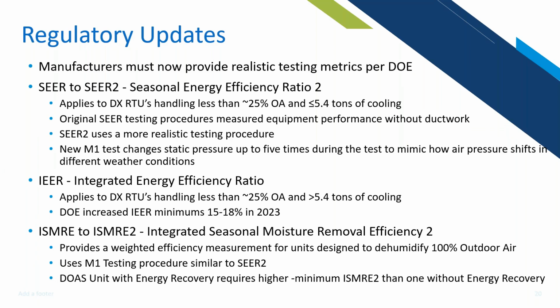Some other changes in regulations: manufacturers now need to provide more realistic testing metrics per the DOE. So you're going to start seeing nomenclature like SEER2. SEER has always been thrown around. It's the seasonal energy efficiency ratio, and that applies to DX rooftop units handling less than 25% outside air and less than or equal to 5.4 tons of cooling. The original SEER testing procedures were not as realistic because they were measured without ductwork, but SEER2 uses the new M1 test procedure that adds static pressure to the system and weights it in a varying way to provide a more realistic performance.